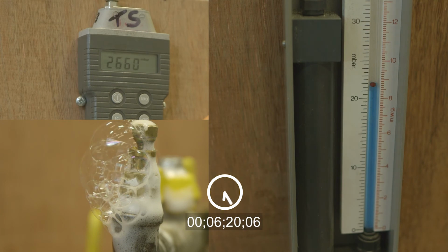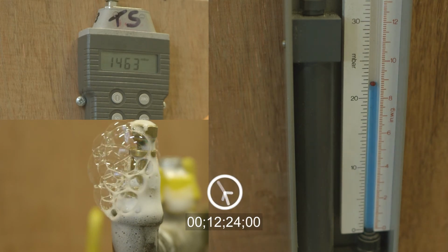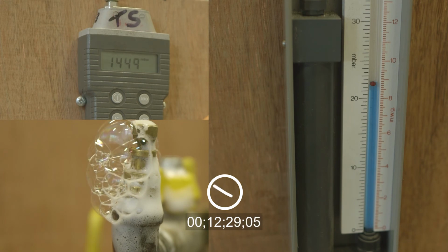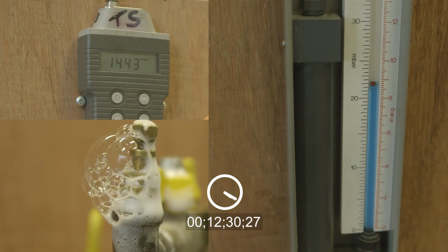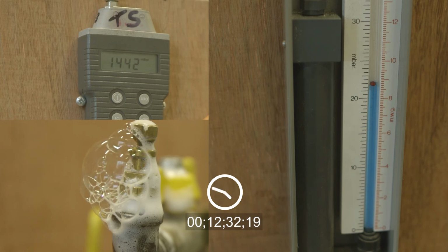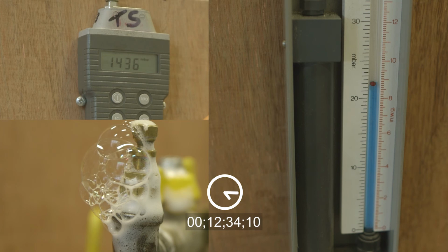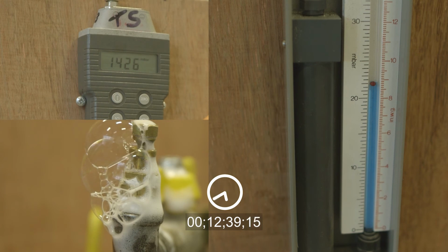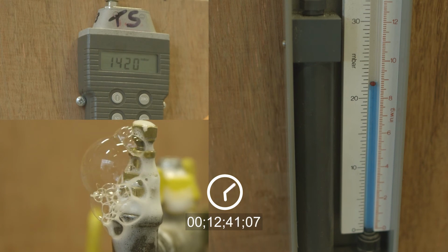This shows that it is the reservoir of pressure that is maintaining the pressure of 22 millibars in the installation, effectively masking the leak. After 12 minutes has passed, we can see that although the leak has been evident from the start, we still have a reading of 22 millibars on the pot meter. You can also see that the pressure in the reservoir is continuing to drop and is currently at 1432 millibars.